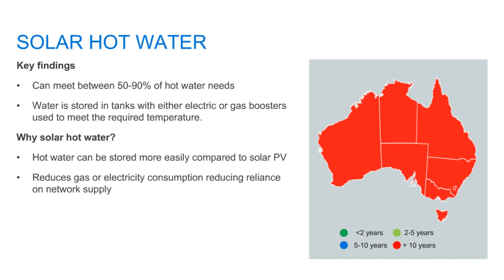Solar hot water is a renewable form of generating hot water for either domestic or potable systems, and it can be used in heating, showers, or other hot water uses. Typically the water is stored in tanks and then boosted using electric or gas boosters to meet required temperatures, either for the temperature of use or to remove Legionella from the system. The paybacks for this are above 10 years typically across the sector.